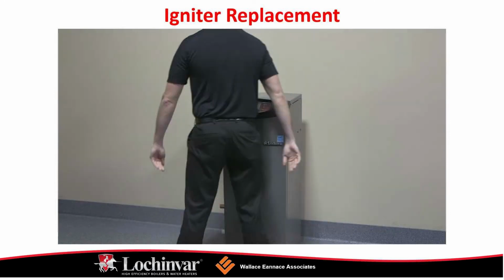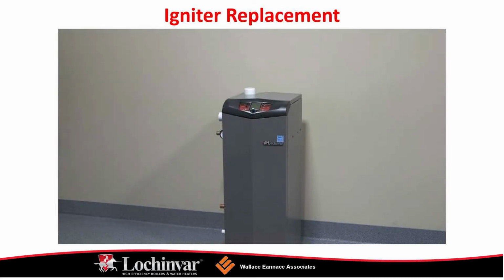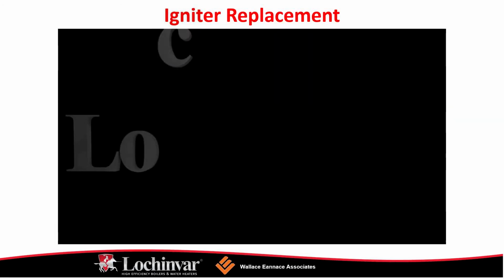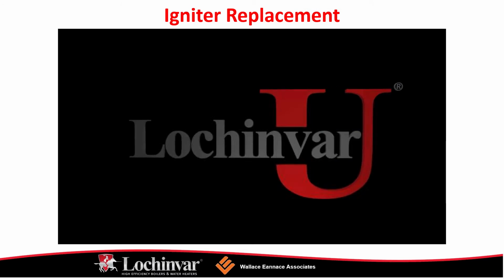The gap between the ground probe and the ignition probe on the replacement igniter is greater than the original to prevent sparking on the upper section of the probe. This can make it difficult to slide the gasket in place. By squeezing the 2 probes together, the gasket will fit properly over the porcelain sleeve. Use care not to damage the gasket. If the gasket is damaged, it must be replaced.